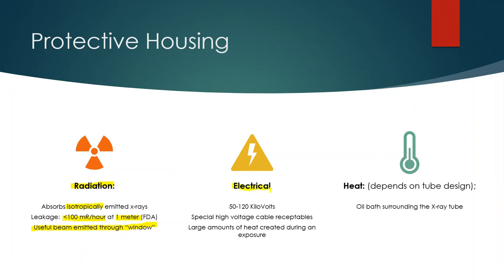The protective housing is not just there to limit radiation — it also protects us from electrocution by the electrical components. We're dealing with anywhere from approximately 50 to 120 kilovolts. To put that into perspective, regular wall sockets run at 110 volts, and large equipment plugs run at only 220 volts. We're dealing with 50 to 120 thousand volts when creating x-rays. For this reason, there are high voltage cable receptacles that plug into the protective housing, essentially eliminating the possibility of electrocution under normal use.